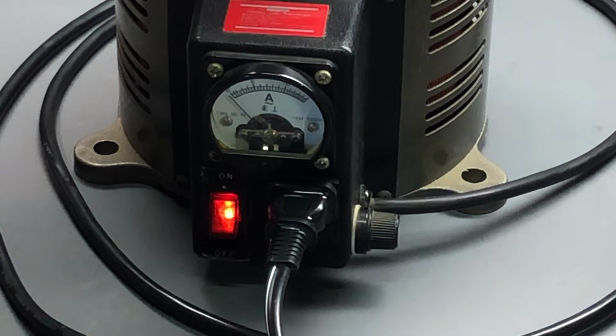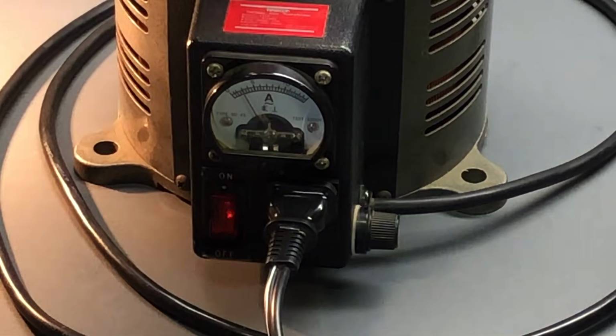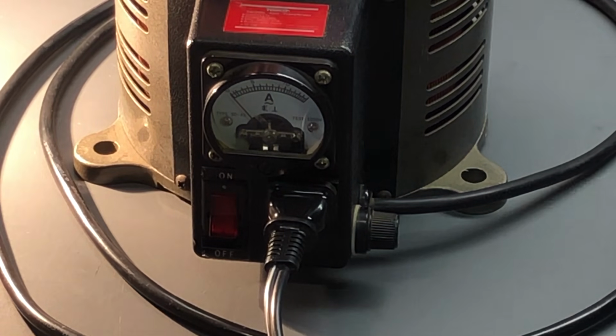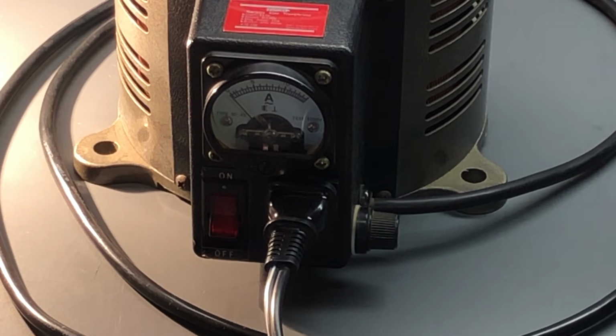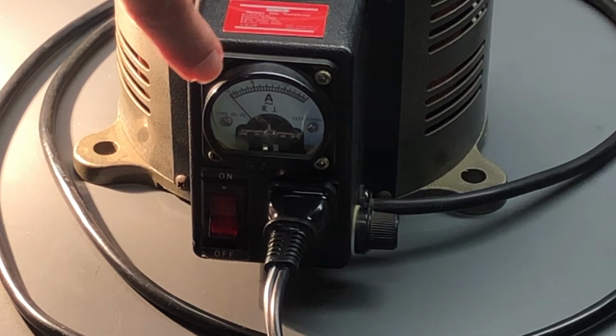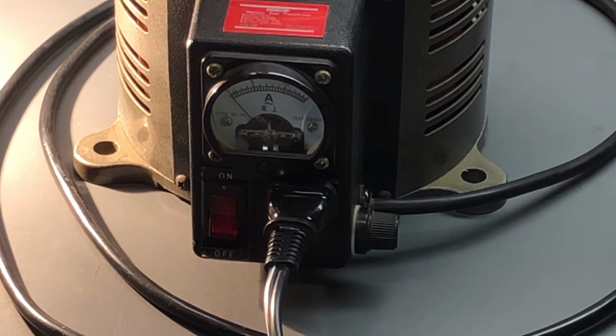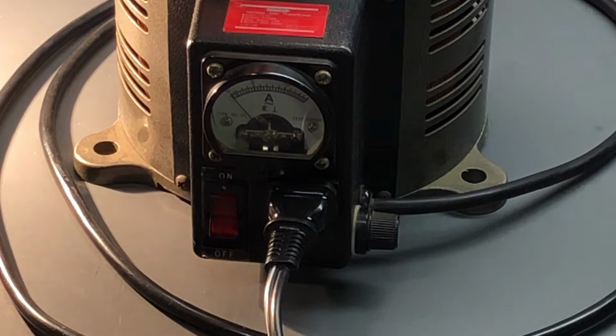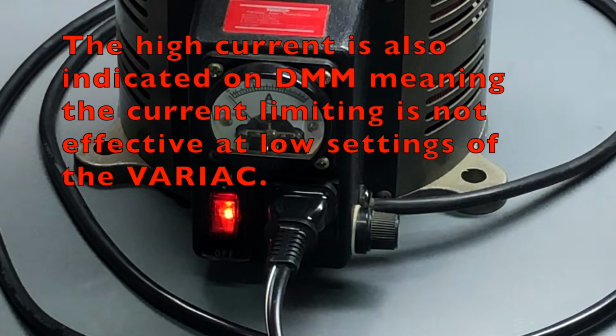You can see it jumps up very high. And then it begins to fall, all right? So right there is 120 volts on the Variac. The incandescent lamp is at full brilliance. And again, there's 0.823 amps flowing on that secondary of the isolation transformer. You would also have roughly the same current flowing over here. So the meter is hardly indicating at all. It's because it's a very low current. But you can see it jumps up very high right there at the beginning. And you can almost hear a little bit of arcing in the Variac because of the higher current flow.